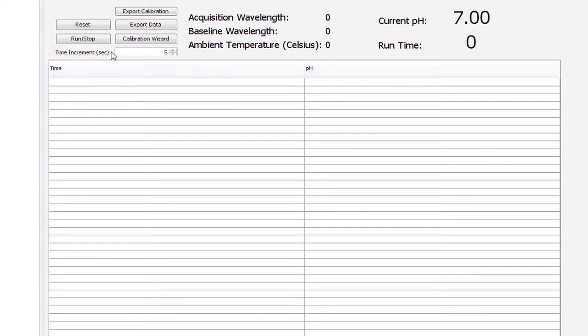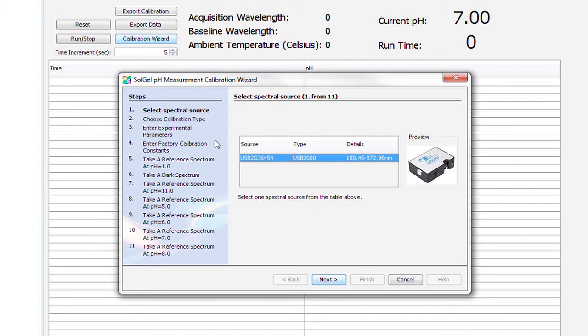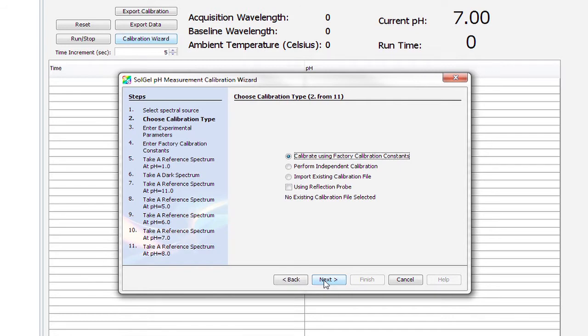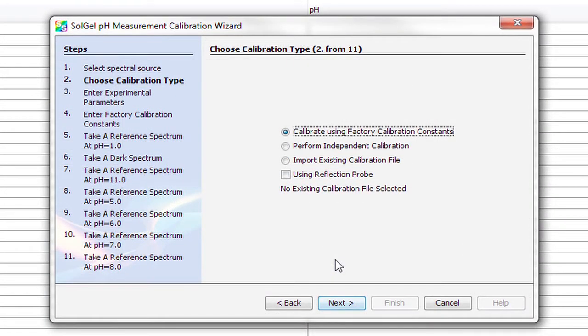Click the Calibration Wizard button in the pH module. Select your spectrometer and click Next. In this tutorial, we'll perform a factory calibration reset, which is your first option. The second option, independent calibration, is nearly identical in procedure, though requires 3 additional reference buffers. If you've run a factory or independent calibration in the past and saved the calibration file, the third option allows you to load this file for fast startup. With Calibrate using factory calibration constants selected, click Next.